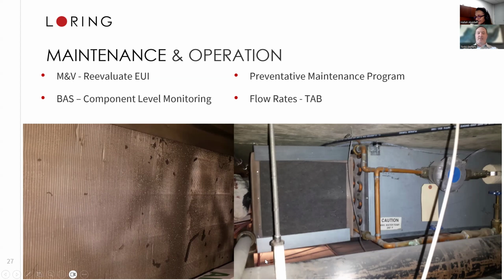A lot of it is things that seem simple but can get overlooked. On the left-hand side is a cooling coil inside of an air handler, and you can see a cross-hatch pattern on there, like big X's. Those are actually areas where the existing building filters had degraded around the edges over a period of what we presumed was 15 years without being changed.